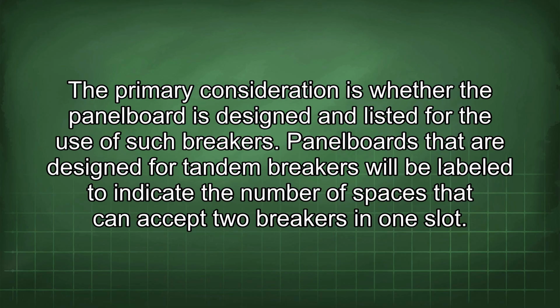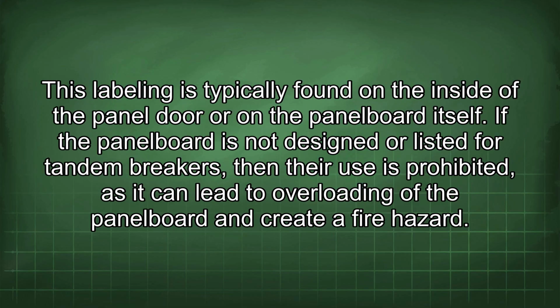The primary consideration is whether the panel board is designed and listed for the use of such breakers. Panel boards that are designed for tandem breakers will be labeled to indicate the number of spaces that can accept two breakers in one slot. This labeling is typically found on the inside of the panel door or on the panel board itself. If the panel board is not designed or listed for tandem breakers, then their use is prohibited, as it can lead to overloading of the panel board and create a fire hazard.